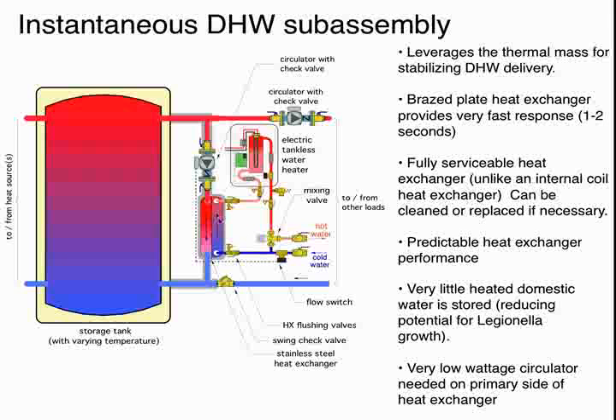We also have very little hot water residing in this system. Once we shut this off, it's really only the heated water that's in the secondary side of the heat exchanger and this piping that's there. And the advantage there is reduced water volume, reduced potential for Legionella.